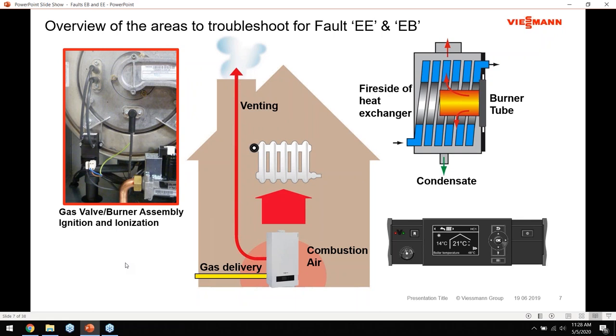Combustion air and venting have a long-term impact on proper boiler operation. If something's not quite right on the venting or combustion air side, you might not see that show up right away - it may take a year, two years, or even three or more years for the impact of improper venting or combustion air to become an issue. We'll look at signs of venting problems and combustion air issues, how to inspect them, and how to address them before they become larger problems.